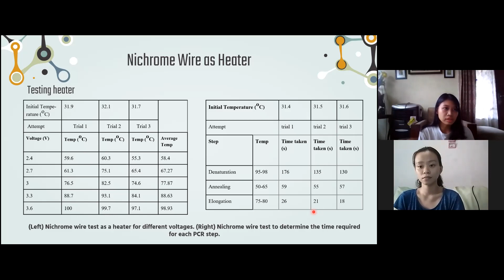So the time that is needed is approximately 2 minutes. And then for annealing, it's just 59 seconds, 55, 57. And for elongation, from 65 to 75 to 80 degrees, it just needs 26 seconds, 21, and 18 seconds. So it's kind of fast for the changes, and the PCR also needs a fast time to change like that. So now we go to the full test.